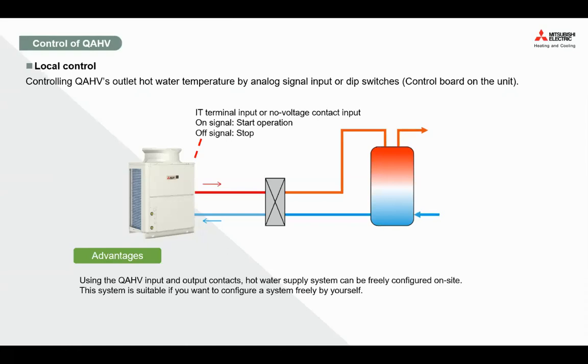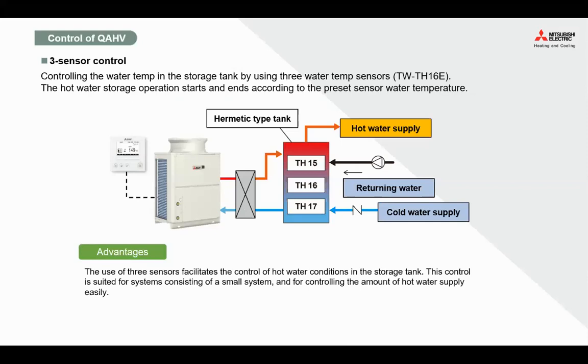Just some more examples. So it can be a very simple control. It can be a non-contact input, right? On to turn on the system, off to turn off the system. So you will have, let's say, a thermistor on the pipe, and the water temperature inside the tank may be too low. Just turn on the QAHV, turn on the pump, and then just recirculate and heat up the water to maintain that level. It can be very, very simple operation. Or you can also have a 3 sensor control, right? Because stratification does happen inside a vertical tank.